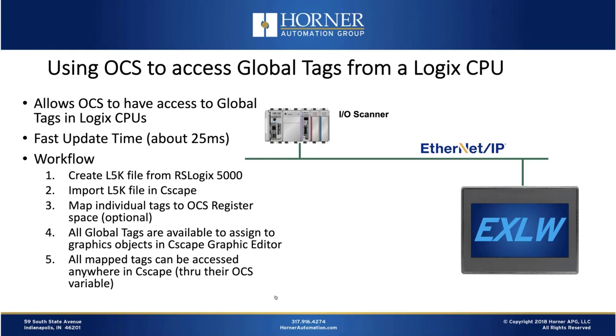The general workflow: you need access to the program in the Logix CPU, or at least an L5K export file from the RSLogix 5000 program. If you don't have control over that program, contact the integrator or customer — whoever does have control — and have them send you a copy of the L5K file. That gives you the ability to access all the tags within the processor. Once you've imported the L5K file, you have the option of individually mapping those tags to OCS register space. And whether you choose to map tags individually or not, as long as you import the L5K file, you have access to those tags from the screen in the graphics editor.